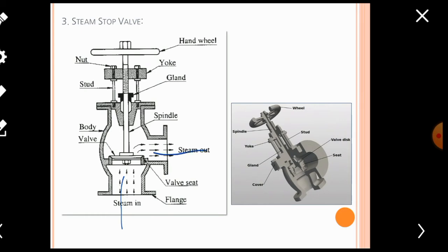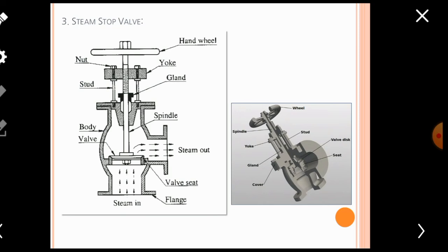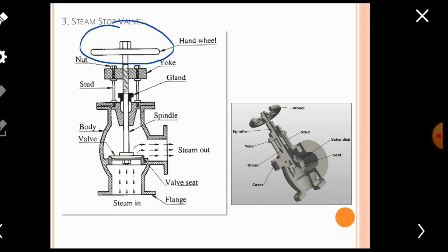The body has an inlet passage and an outlet passage for steam. Connected to the body by studs and nuts is an important part called the yoke. There is also a black-colored gland, which is provided to prevent leakage of steam coming out from the steam stop valve. The central spindle has a valve at one end that sits directly over the valve seat, while at the other end there is a handwheel operated by the boiler operator.